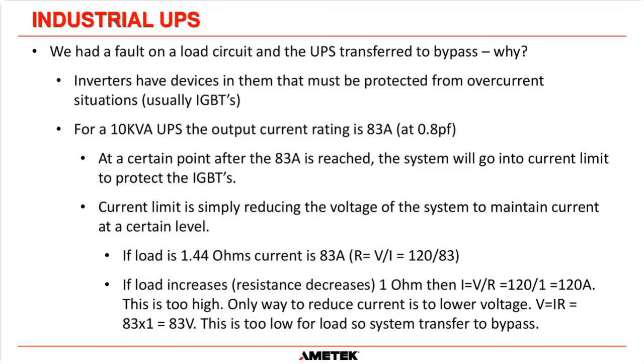So what the UPS is going to do is transfer to bypass. When it sees the voltage of the inverter going down too low, and it's doing that to protect its IGBTs, the system says, okay, voltage is too low, let's transfer to bypass. The bypass is a much more robust, solid supply of power, and it can do whatever it needs to do to clear that fault on the output. Then you will have to go back to the UPS and transfer the system back to inverter once you've got rid of that load problem. Hopefully that explained current limit and didn't confuse you more than necessary.